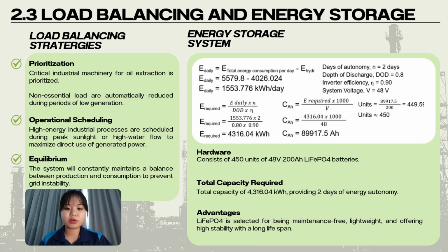Moving on to the energy storage system, the hardware consists of 450 units of 48 volt, 200 ampere-hour LiFePO4 batteries. The total capacity required is 4,316.04 kilowatt-hour, providing 2 days of energy autonomy. The advantage is that it is selected for being maintenance-free, lightweight, and offering high stability for a long lifespan.